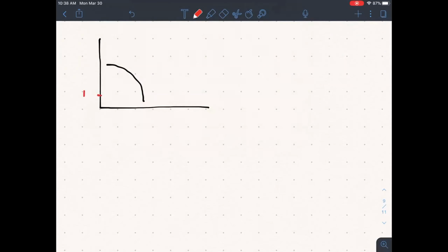So it starts at 10. So 10 meters is basically when nothing's running, we have that head difference of 10 meters. So when there's zero discharge, the pump would have to overcome 10 meters. So that's 10, and then the system curve would look something like this.